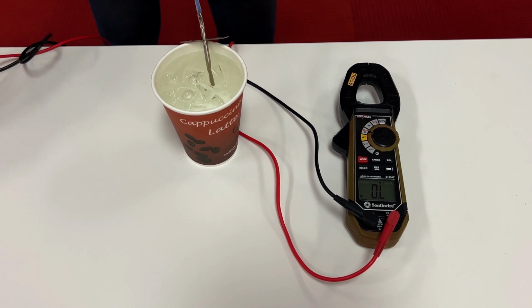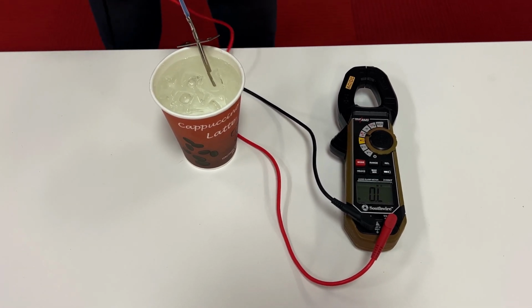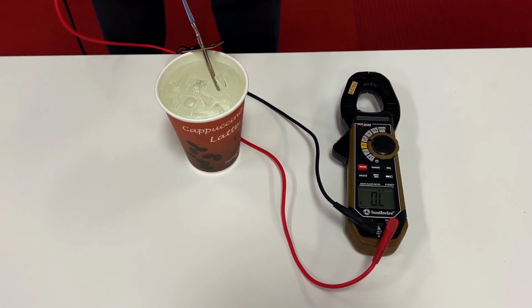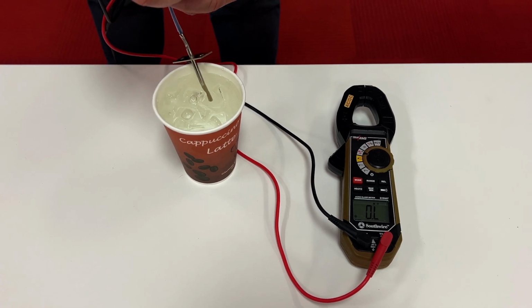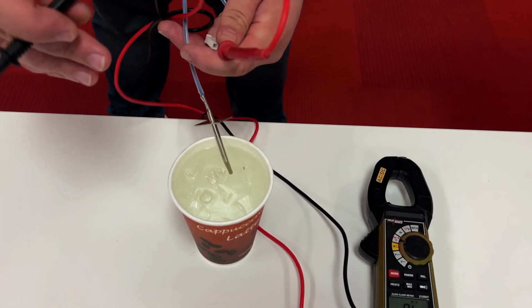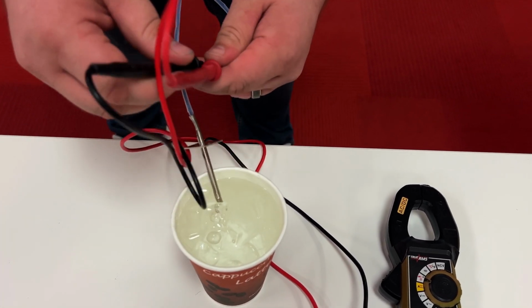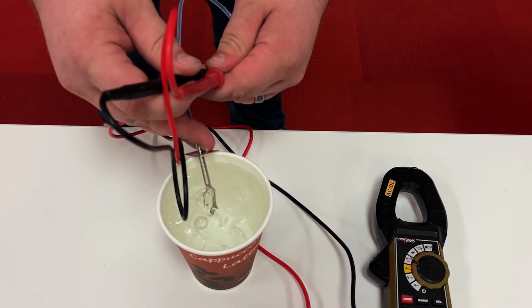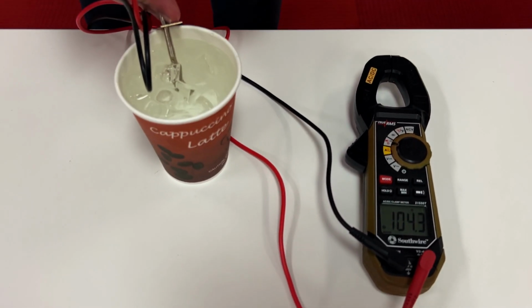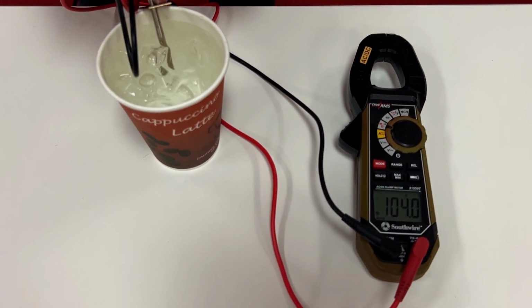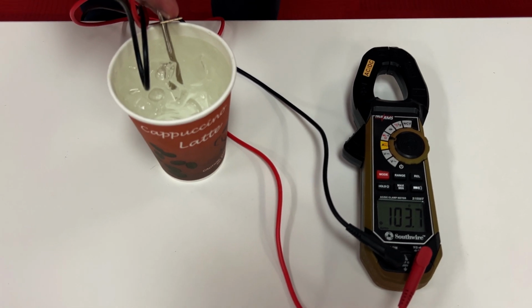As it's soaking, you're going to use your multimeter. You can use any multimeter you like, as long as it has the ability of measuring resistance. And you're going to connect it to both sides of the RTD. And you can see we're starting to get a resistance value there on the meter. As the probe soaks, you should see that resistance slowly start to drop.